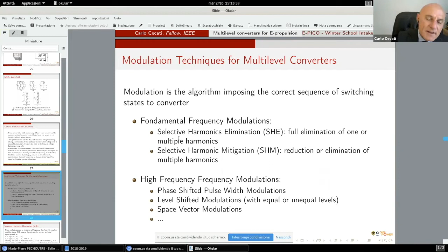Modulation is divided into fundamental frequency modulation, meaning the motor is supplied by a voltage staircase where the frequency of this staircase is exactly the same as required for motor operation. So if the motor must be supplied with a sinusoid at 50 Hz, we have waveforms which replicate a 50 Hz staircase waveform. If we need 100 Hz, we have 100 Hz without any high frequency modulation. This basic fundamental modulation is usually divided into two distinct approaches.